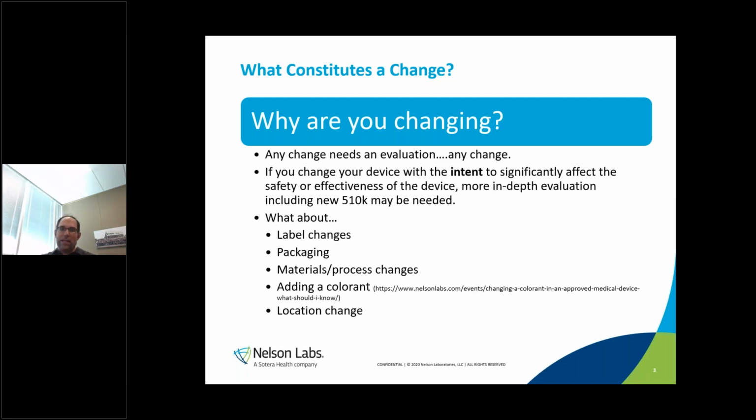Lots of times in my past, we've seen changes of packaging, for example, and the individual company decided not to do any testing because they determined that the packaging had no impact on the biocompatibility of the device. We know that packaging leaches chemistry that could be transferred to the device. We've seen ink that has leached off of a label and interacted with the medical device. So there are times where you may not consider the change to be even one to think about and just pass over, and that's the risk.